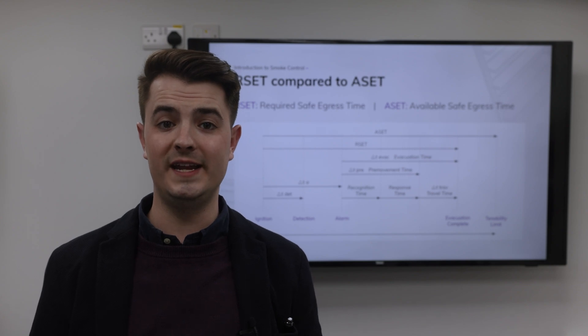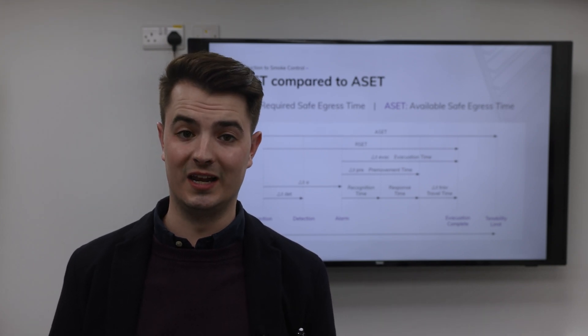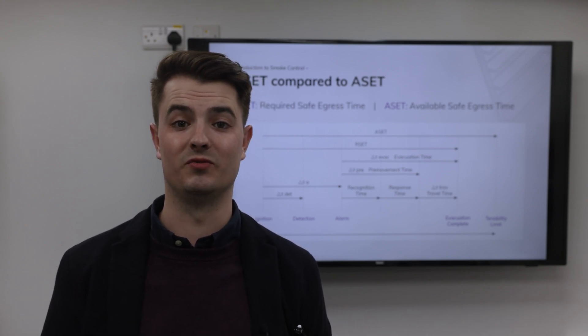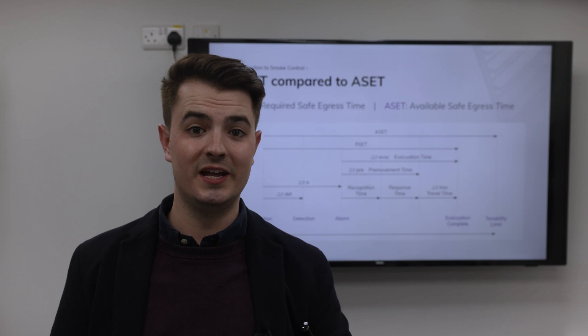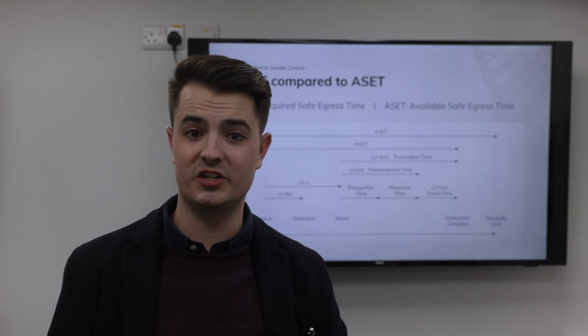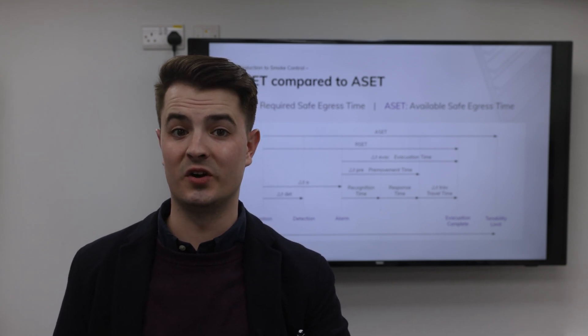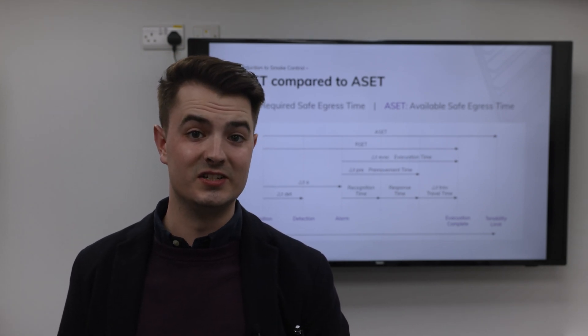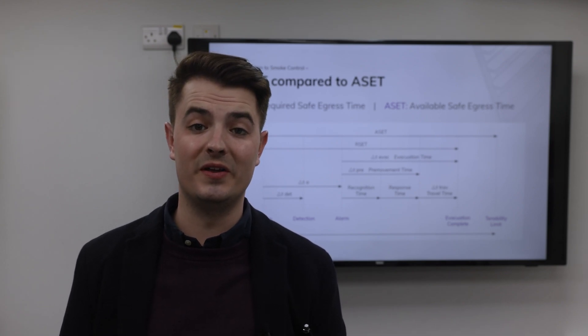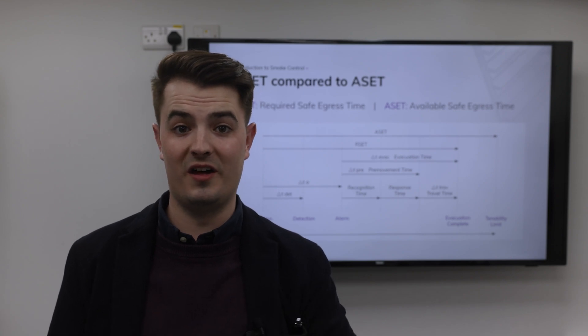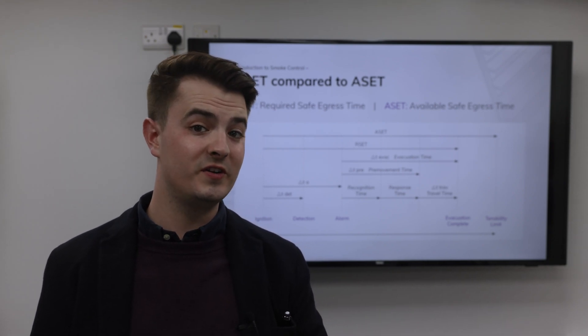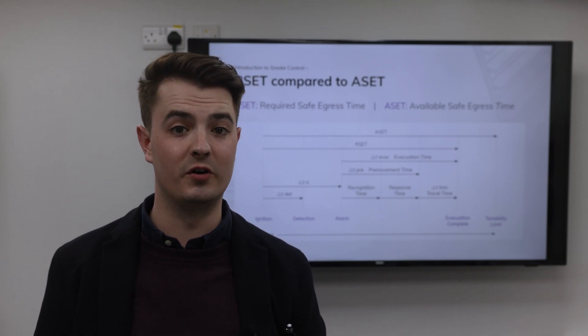Next, pre-movement time. This is the time an occupant needs to recognise the situation and react to the alarm. Recognition includes the time required to get an occupant to take fire alarm cues seriously and recognise that some response to the emergency is required. Response consists of a range of activities such as investigating to find the source of the fire, warning others, saving possessions, gathering children and family members, deciding on an exit route, and potentially fighting the fire. The pre-movement time is subject to influences such as the level of assistance in an emergency evacuation — for example, a managed evacuation — the level of fire safety training undertaken by the occupants, the type of occupants (whether they're awake or sleeping, familiar or unfamiliar with the building, e.g., a hotel), or whether the building is fitted with a PA or voice alarm system to guide occupant behaviour.